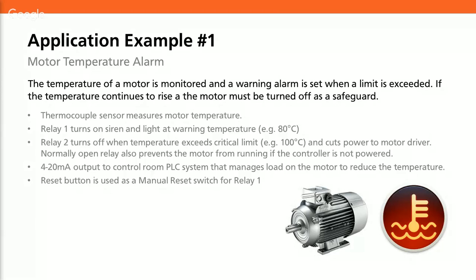So if the motor reaches 80 degrees C and nothing happens, it keeps getting hotter, then the Merlin can eventually act as a safety cutout. The other nice thing about the relays is they are normally open, which means that when the unit is unpowered and in its passive state, the relays will not be closed. So if you use the relay as an enable, then you can also prevent the motor from running without the controller plugged in.